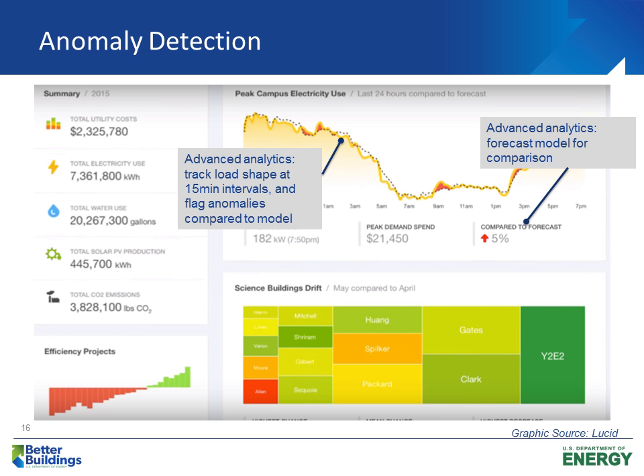If you think about it, we have a projection of energy use hour by hour, shown as this dotted line. If your actual energy use goes over that projection by a certain percentage, you could flag it and say something's going on here, I'm 20% higher, or whatever threshold you want. So you can use that M&V process for hour-by-hour anomaly detection, or accumulate that energy waste and flag it once it's above a certain dollar amount, so you can look into it more. This is a really powerful use of energy information systems, and it would be considered an advanced EIS.